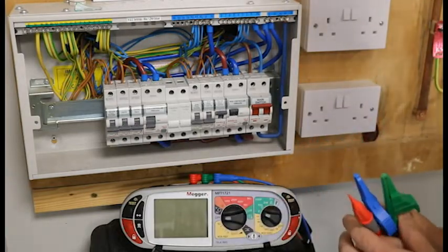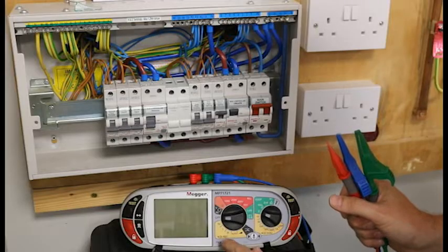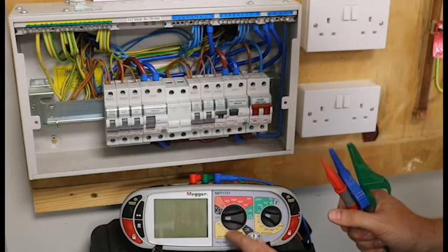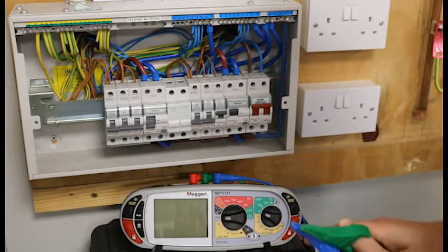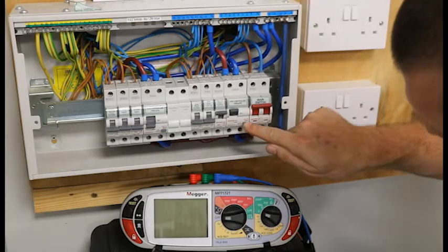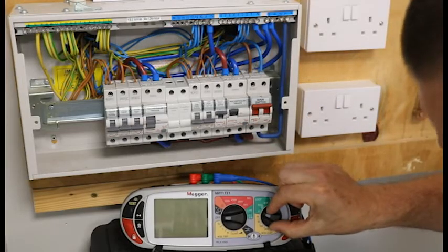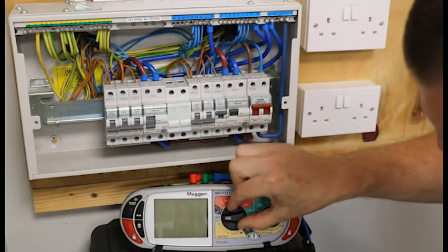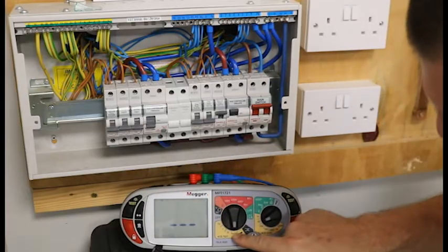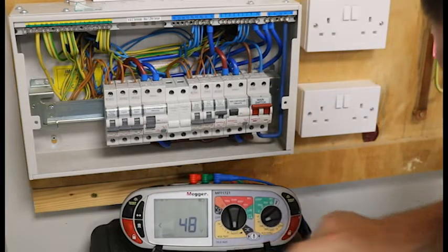To set up the machine we are going to be doing RCD testing, so on this Megger we are going to use the yellow sections. My RCD is a 30mA, so I will set it to 30mA. What is nice about this machine is I have an auto function, so I will turn to the auto function.